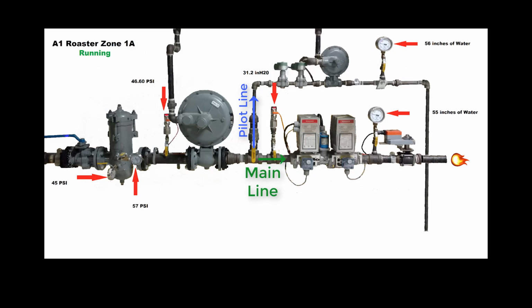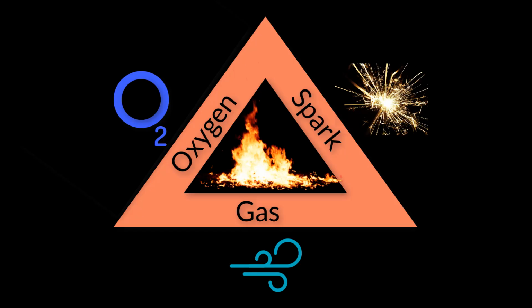For the pilot line, once the gas has passed through the blocking valve, it is then fed into an additional regulator. There is a vent connected to the regulator to expel any excess gas buildup. The gas is then fed to a pilot, which is lit by an ignition transformer that is controlled by the FSR. The ignition transformer sends a high voltage to a spark plug in order to create a spark. When oxygen, gas, and spark meet, then the pilot is lit.